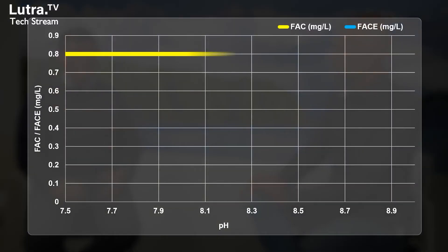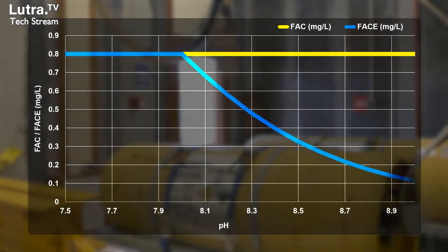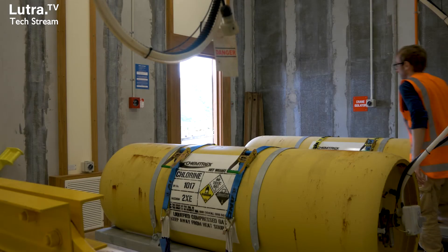Online monitors might speed things up, but they're not necessarily going to give you a real-time 'I've got a problem now' alert. What online monitoring tells you is that if I get an event, I know where it's going to go, I know what the limits are so I can deal with it. It's about preempting what's going to happen - either by reducing your intake, increasing your chlorine dose, your UV dose, or whatever you're going to do. When there are events, you need to increase sampling frequency to perhaps three or four tests over an eight-hour period.